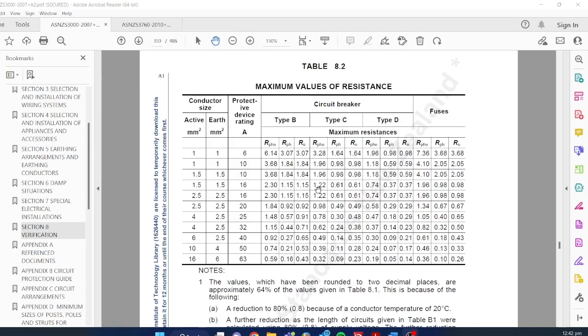So if I look down this column, type C, RPHE, 2.5 millimeter cable, 20 amp circuit breaker, you will see the maximum resistance for the earth and phase together is 0.98 ohms, or roughly 1 ohm. And that means that the phase conductor is allowed to be 0.49 or half an ohm, and the earth conductor is allowed to be 0.49 or half an ohm. Our reading for the phase and earth together was around 0.3, 0.4 ohms. So that is a perfectly acceptable test. We have passed the test on that one. As I said, if you've done this test on that socket, you will now go around and do the test on every socket in that house, everything that you can find.